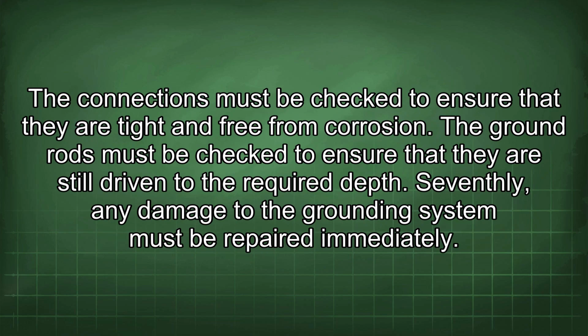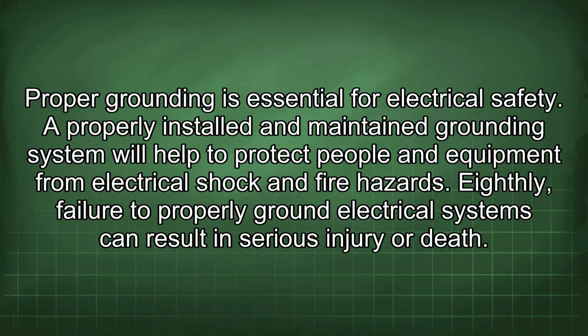Sixthly, the grounding system must be inspected regularly to ensure that it is in good condition. The connections must be checked to ensure that they are tight and free from corrosion. The ground rods must be checked to ensure that they are still driven to the required depth. Seventhly, any damage to the grounding system must be repaired immediately. Proper grounding is essential for electrical safety. A properly installed and maintained grounding system will help to protect people and equipment from electrical shock and fire hazards.